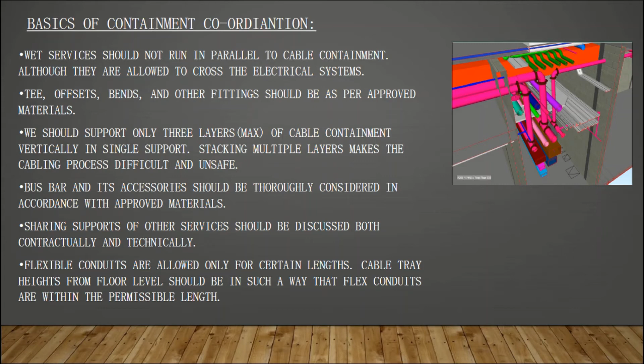The cable tray heights from the floor level should be in such a way that the flexible conduits are within the permissible length. The support system for the services running below and above the trays needs to be planned in advance. The containment should not obstruct the supports. The bend radius of a tray or ladder should be as per the cable laid. Minimum bend radius is very critical to maintain the structural integrity of the cable. The panel height and the tray height should accommodate the minimum bend radius of the cable.